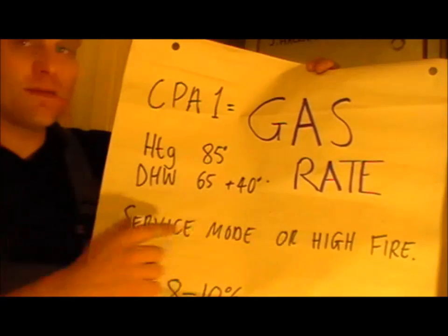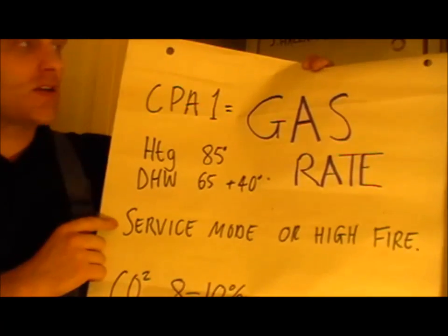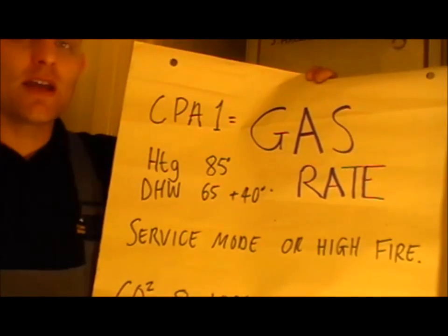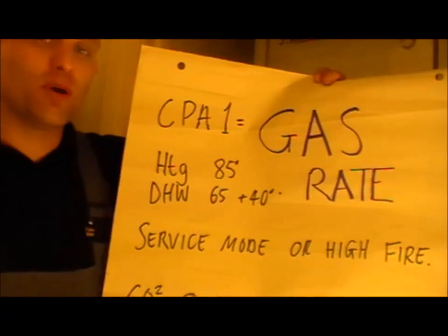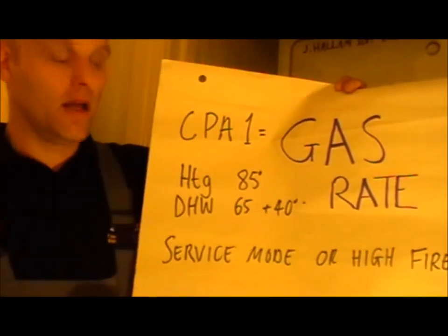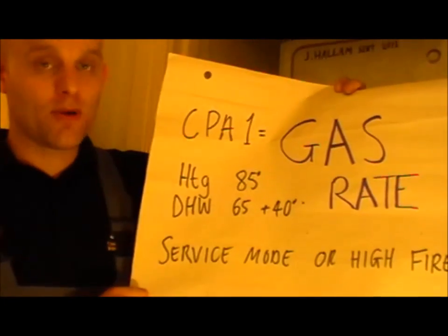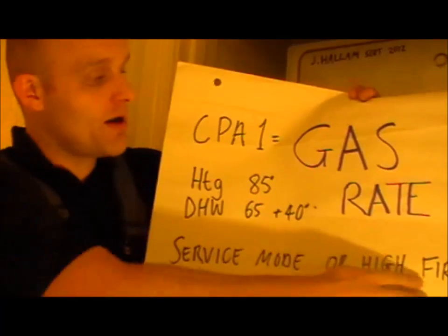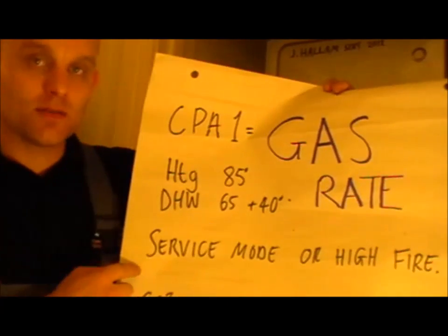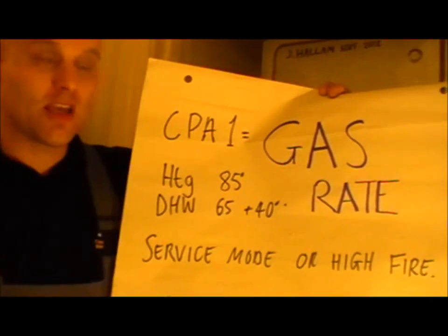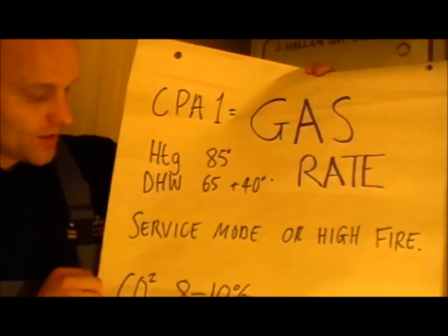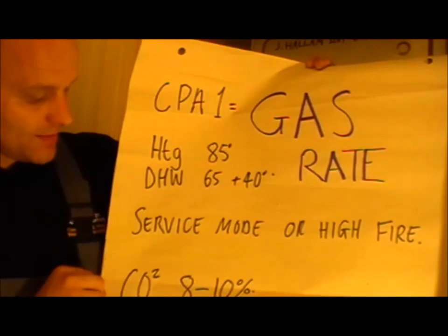When you do a gas rate, always put it on high fire — so bring it into hot water mode so the burner is working its hardest and burning the most gas possible, so you get a proper reading. If you can't put it in high fire, maybe there's a service mode button where you have to press two buttons at once, for example.